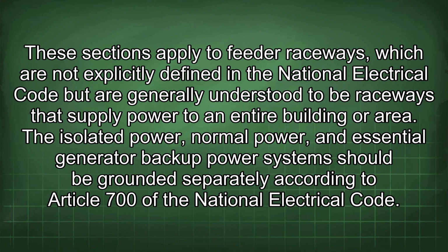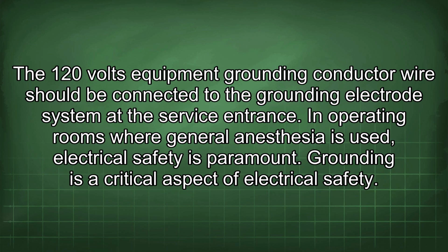The isolated power, normal power, and essential generator backup power system should be grounded separately according to Article 700 of the National Electrical Code. The 120 volts equipment grounding conductor wire should be connected to the grounding electrode system at the service entrance. In operating rooms where general anesthesia is used, electrical safety is paramount. Grounding is a critical aspect of electrical safety.